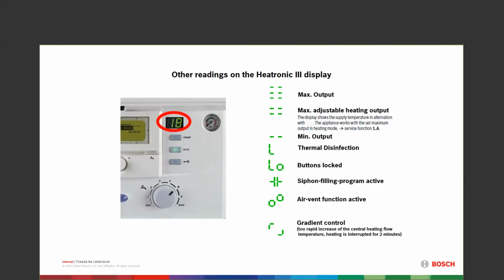Gradient control doesn't show up very often on this. If there's too rapid of an increase on the flow temperature or system side, it's going to turn the heat off for 2 minutes. We don't see it very often. What we often see is the boiler going to 199 or to block limit on that. So gradient control, we don't see that often, but occasionally we will.